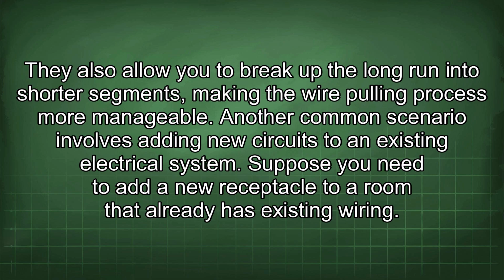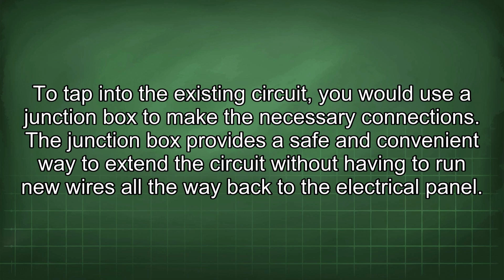Another common scenario involves adding new circuits to an existing electrical system. Suppose you need to add a new receptacle to a room that already has existing wiring. To tap into the existing circuit, you would use a junction box to make the necessary connections. The junction box provides a safe and convenient way to extend the circuit without having to run new wires all the way back to the electrical panel.